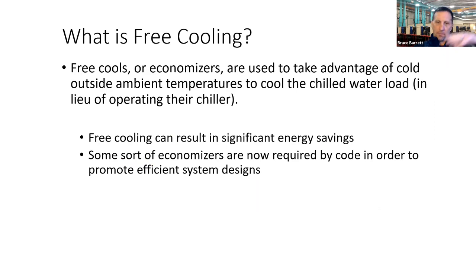So free cooling, it's kind of backing up a little bit. A lot of areas require free cooling or economizers to take advantage of the cooler ambient temperatures outside. It can be very, very significant savings. Not only in dollars and energy, when we're just doing free cooling, we're operating the pump still, we're operating fans, but we're not starting compressors. It can also prolong the life of your equipment when you're not turning compressors on, say at 0 degrees or minus 10 degrees outside, and having that danger of flooding your compressors with refrigerant. A lot of local codes do require this design.